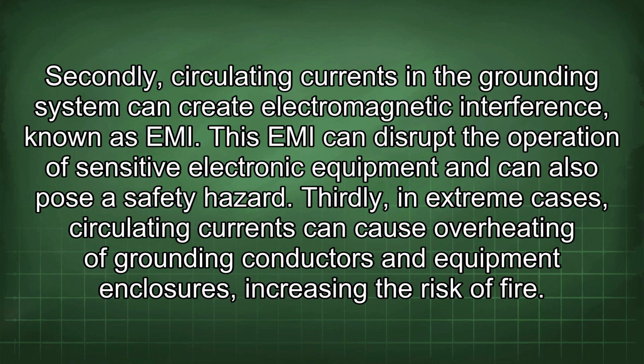Secondly, circulating current in the grounding system can create electromagnetic interference, known as EMI. This EMI can disrupt the operation of sensitive electronic equipment and can also pose a safety hazard. Thirdly, in extreme cases, circulating currents can cause overheating of grounding conductors and equipment enclosures, increasing the risk of fire.